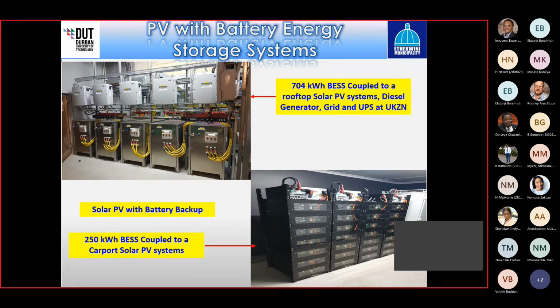It's obviously coupled to the grid and has a UPS as well at UKZN. So this typically feeds the university's IT network and servers so that it's not affected by power outages or disruptions on the network. And then the bottom one is a 250 kilowatt hour battery energy system that's coupled to a carport solar PV system. And this is typically used to feed the customer that has critical load, also with his diesel generators there.